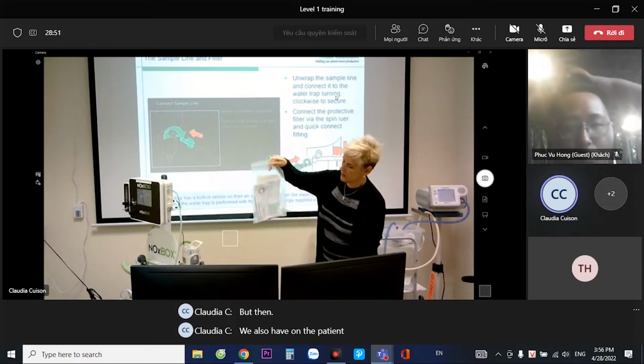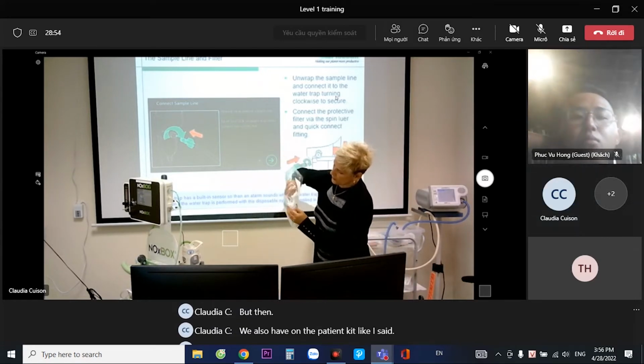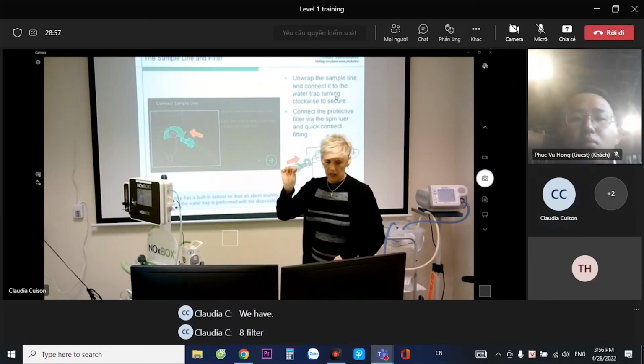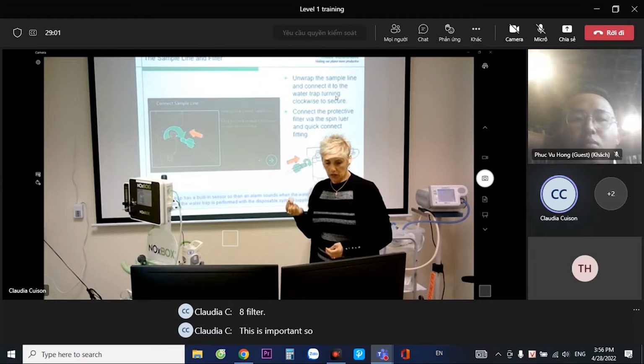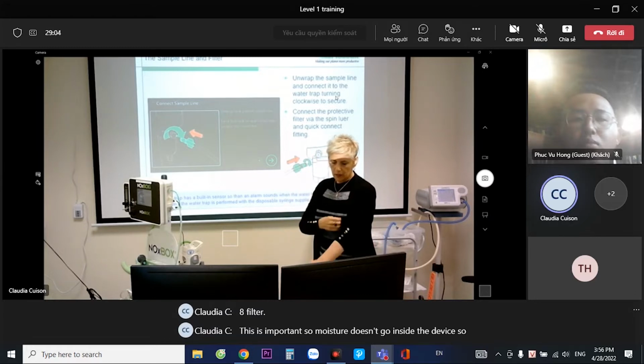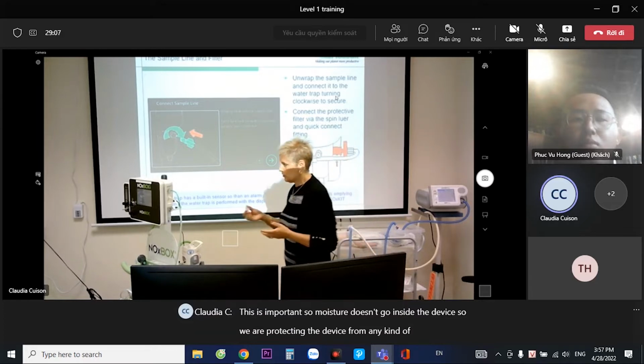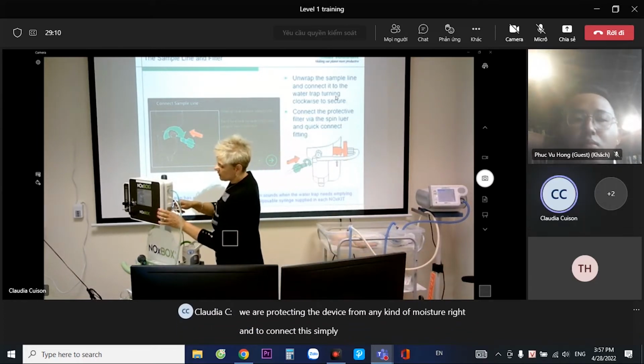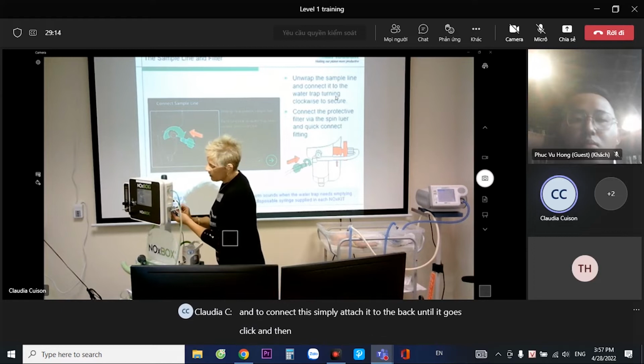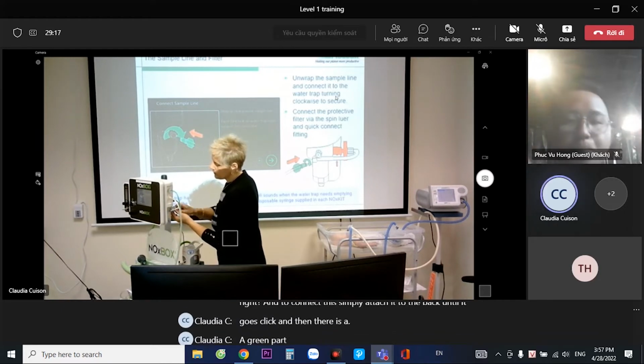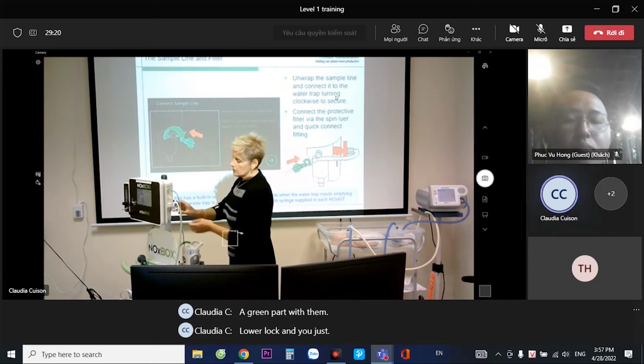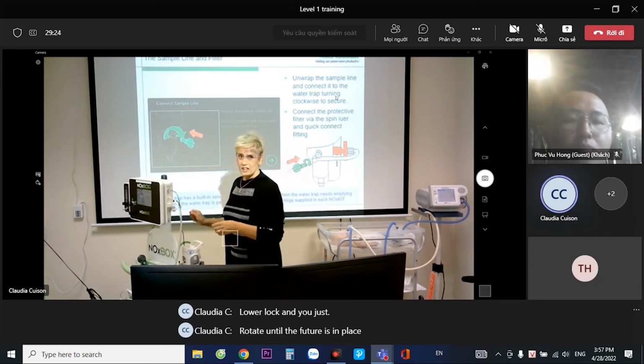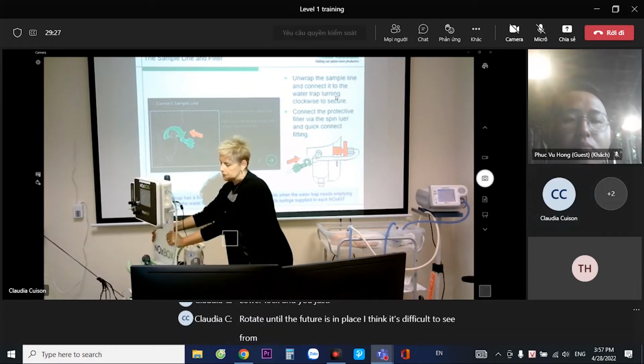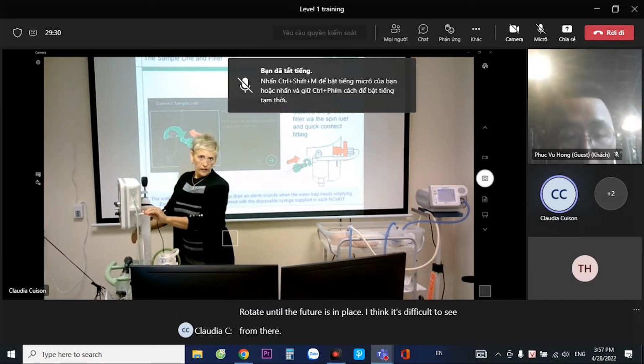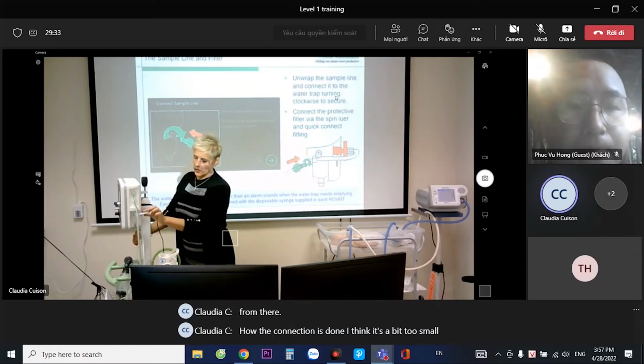We also have on the patient kit, like I said, a filter. This is important so moisture doesn't go inside the device. So we are protecting the device from any kind of moisture, right? And to connect this, simply attach it at the back until it goes click, and then there is a green part with a lower lock, and you just rotate until the filter is in place. I think it's difficult to see from there how the connection is done. I think it's a bit too small, but it's this one.